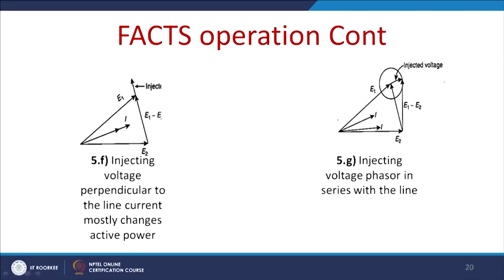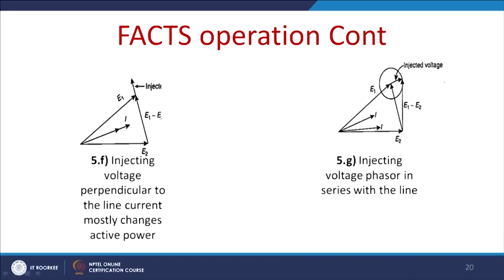Now, we can inject voltage perpendicular to the current. Then that helps us to change basically the phase angle. So, when we inject voltage perpendicular to the line current, it mostly changes the active power of the system, and when we inject voltage in series with E1, almost in phase in the phasor diagram, then voltage regulation can be done by this method.